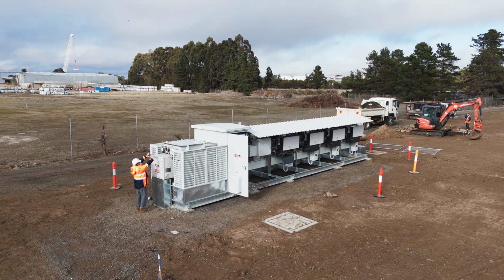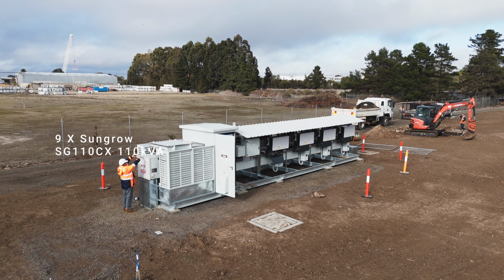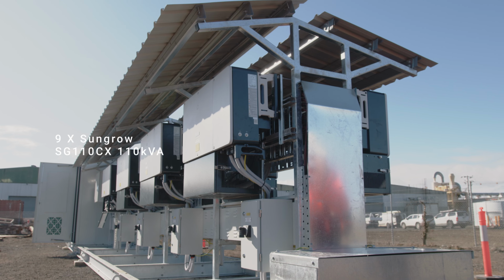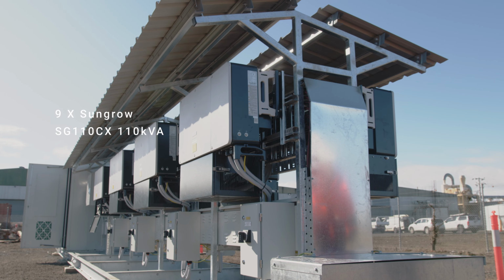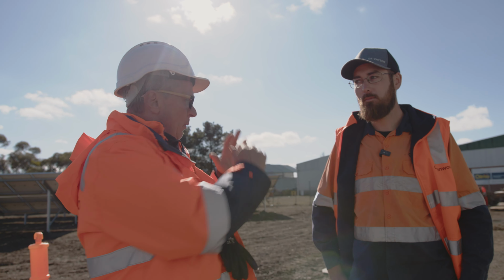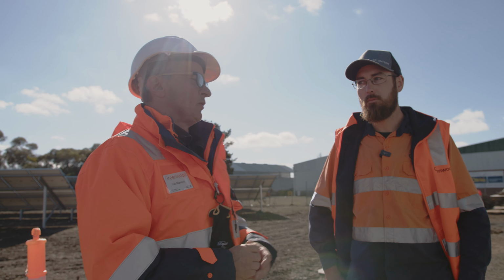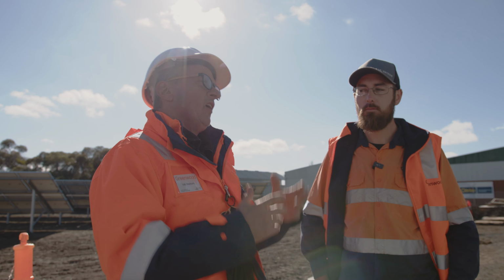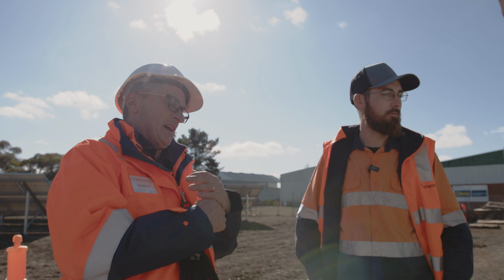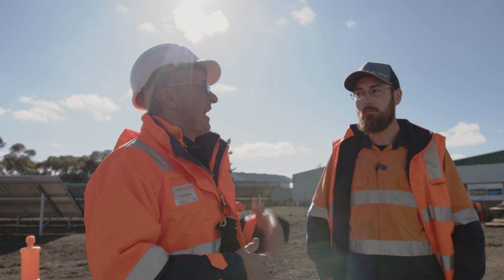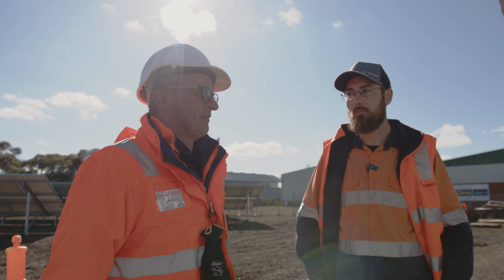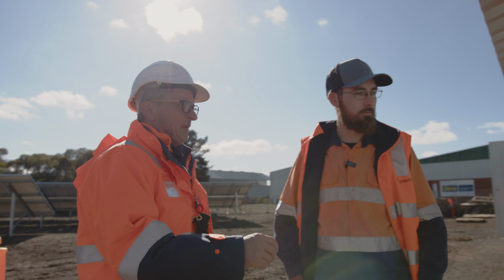So on this site we've got 9 Sungrows. They're each 110 kVA, so cumulatively 990 kVA. And I know the transformer, and we'll get to that. It's a 1 MVA transformer, obviously, because it needs to be above the actual cumulative capacity of the inverters. Let's move on down a little bit further.